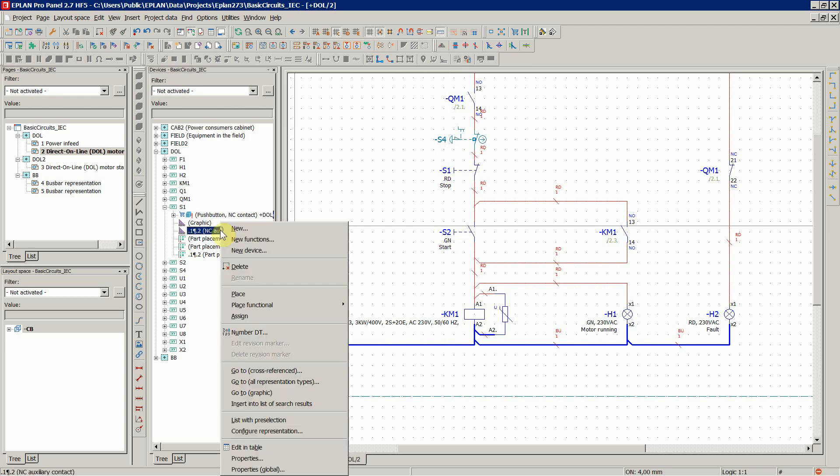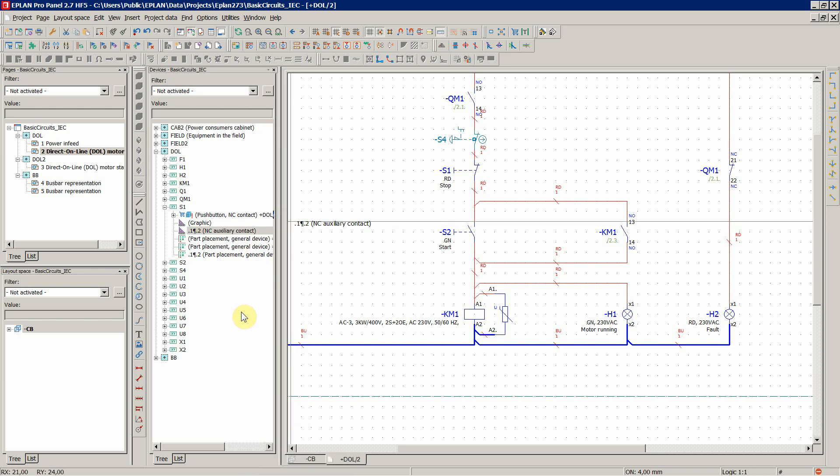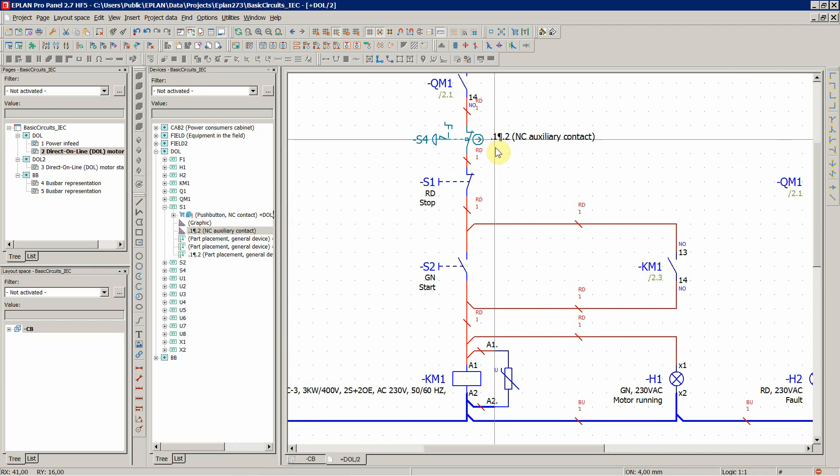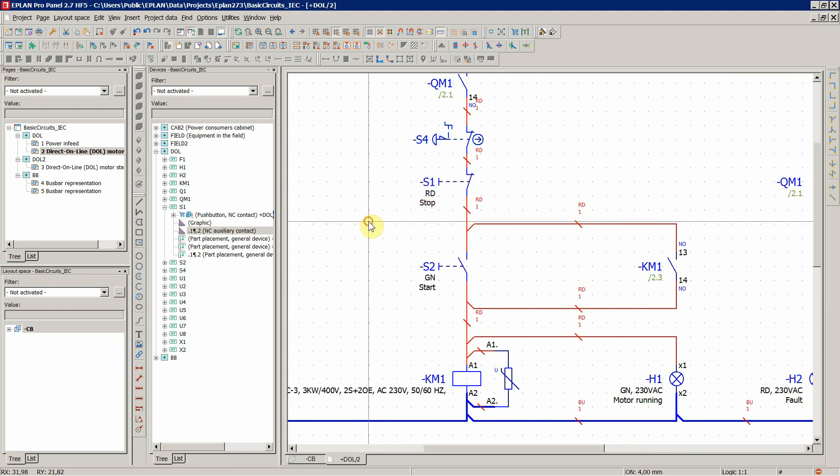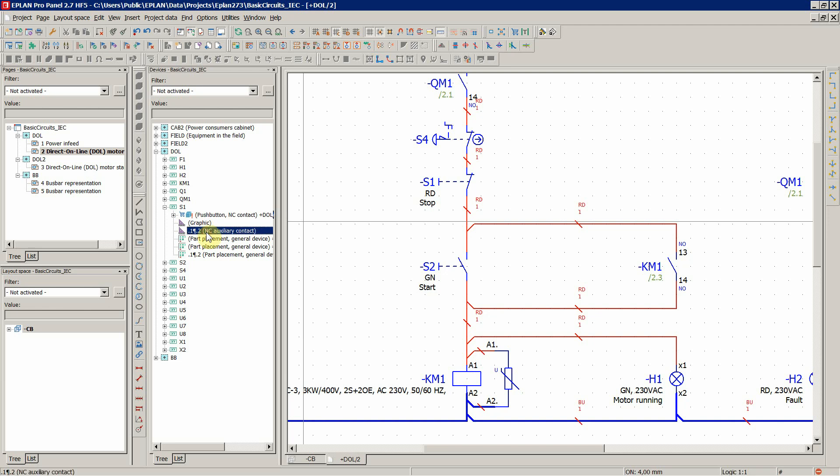And we defined it as a push button normally closed contact. So when I try to assign this S1, it's gonna say does not match the selected function definitions. So to solve this, you basically have two options. The first one is to change the function definition of this one and say that this is an auxiliary contact, or to change this one in the part number, official part number from Siemens, and call it a push button.